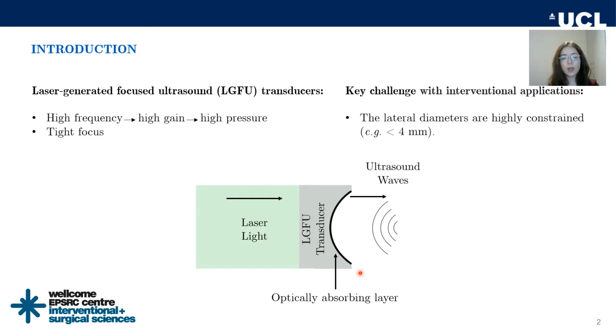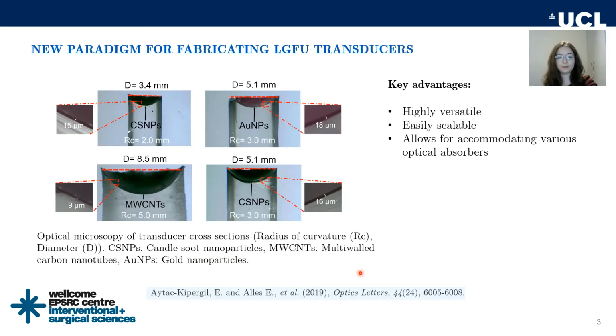interventional devices. But the lateral dimensions of these devices, such as catheters, are highly constrained and mostly less than 4 millimeters. And as the transducer diameter gets smaller, it becomes more difficult to reach the therapeutic levels of ultrasound because the materials have a certain damage threshold, so there is a limit in the excitation light energy. To overcome all these challenges, we are exploring fabrication methods that allow for producing transducers at a desired dimension and also exploring their capabilities at smaller scales.